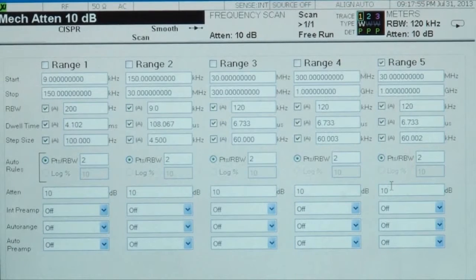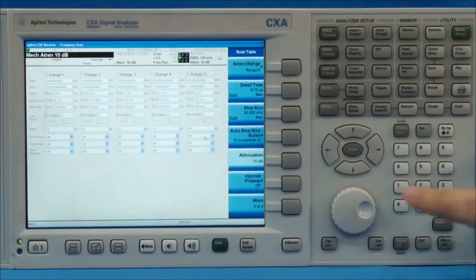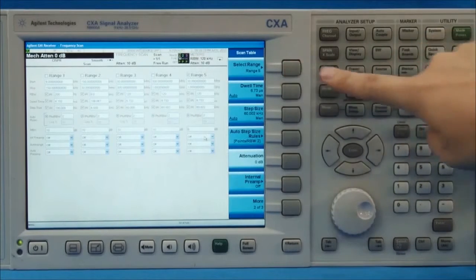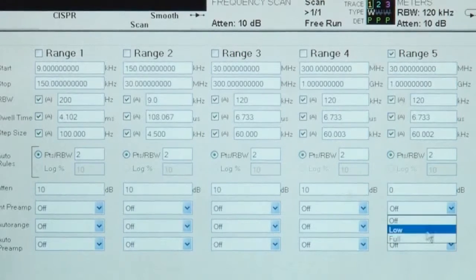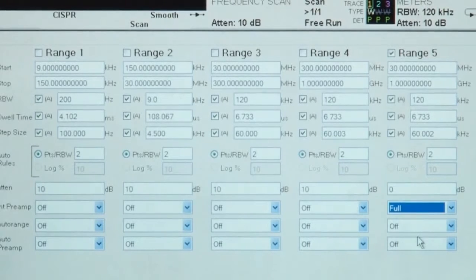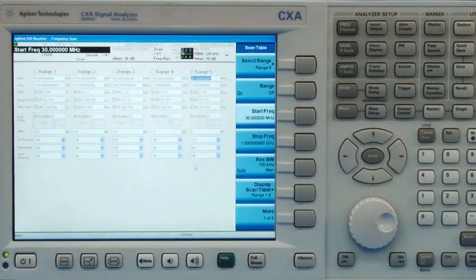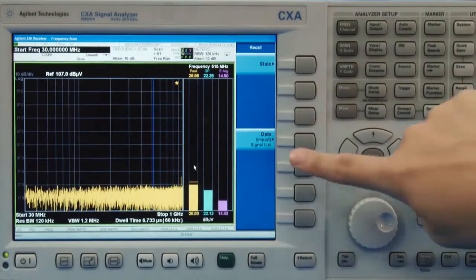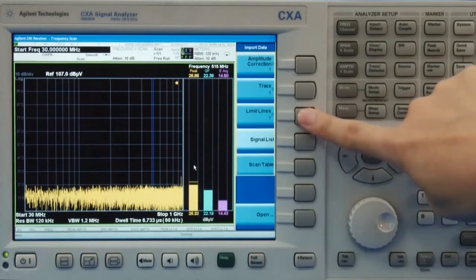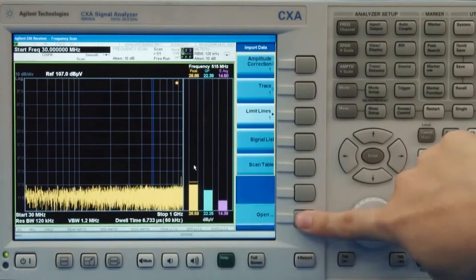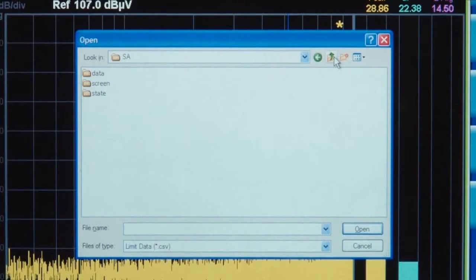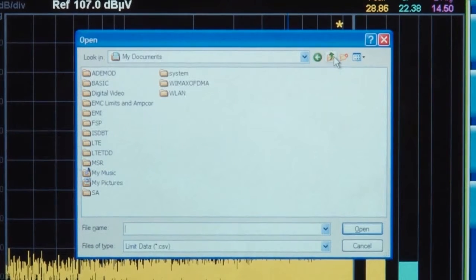Radiated emissions are usually low-level signals. Therefore, we set the spectrum analyzer to its best sensitivity — set attenuation to zero and enable the full pre-amplifier. When conducting a far-field EMI pre-compliance test, we can recall the limit lines which are pre-installed in the instrument according to the EMC standards. For instance, in this case, we choose the EN 55022 standard, which applies to laptops.